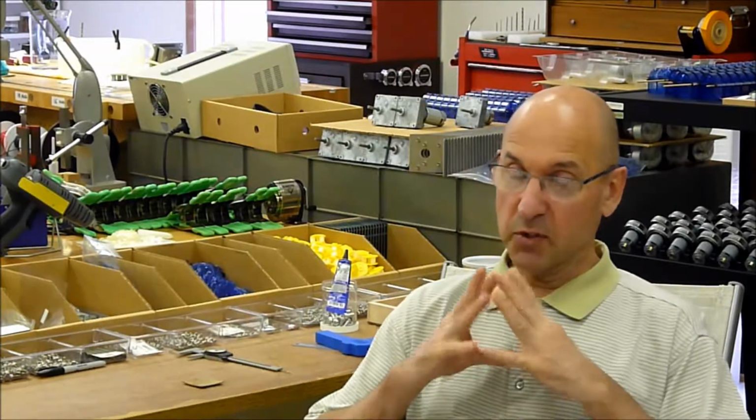So here is a real-world example of Ohm's Law at work, making our shop more safe. So when we first moved into the facility here, within the first month, our lights went out. And so I do have a little bit of electrical background, and so I pull the power panel off. The fuse was not blown, the breaker was not tripped, but the wire going to the breaker that was controlling the circuit of lights was obviously charred, melted, burnt, not a good sign. So that was the problem. So we had no lights, and the wire was melted off the lug on the power panel.